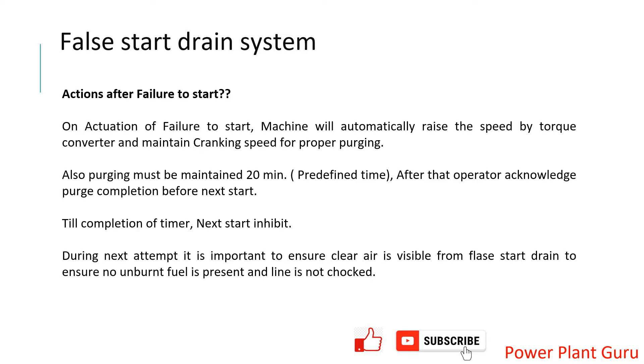Once it has failed to ignite, there may be some fuel accumulated in the turbine which needs to be purged out. The machine will automatically go to cranking speed, which is required to purge the remaining fuel with higher air pressure. A 20-minute purging cycle will be completed, where the volume of air passing through will purge out whatever remaining fuel is there. After that you have a signal that you can go for the next start; until that time the start signal will be inhibited.